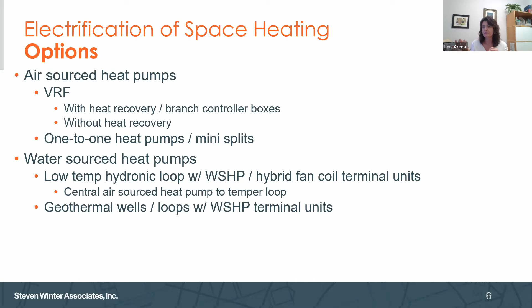And then there's the water source heat pump options for hydronic loops. You can do a low temp hydronic loop with an air to water heat pump that charges that low temp water loop and then feeds water source heat pumps or hybrid fan coil units in the apartments. Or you can do geothermal wells that provide the boosted temperature in the water loop, and again use water source heat pump terminal units in the apartments or spaces - I always think multifamily, sorry.